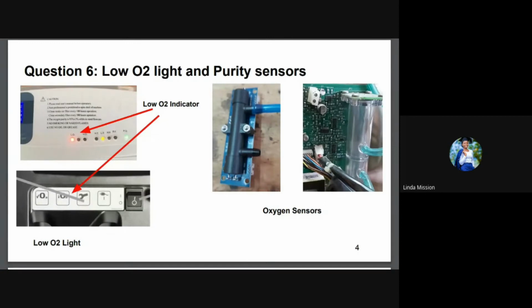So to solve the problem, you have to trace the connections between the oxygen sensor and the control board and check for continuity using a multimeter, and also inspect for any visible disconnection along the traces or wires to the sensor. If there is disconnection, take the right step to connect the circuit, and this can be done by soldering the sensor on the board if the connection is through soldering, securing the sensor through plug-in if plug-in connectors are used, and also replacing cables if the connection between the sensor and the board is through cables.